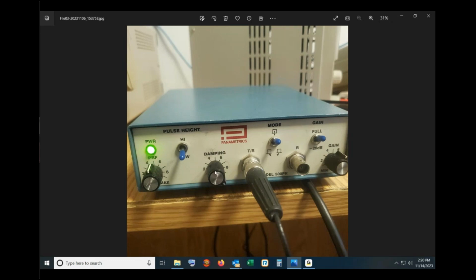Here we've got the damping, which controls how wide the pulse you excite with. So you can change the shape of your ultrasonic echoes that way. And then we've got a gain here, which allows you basically a volume button to increase or decrease the amplitude of the echoes.